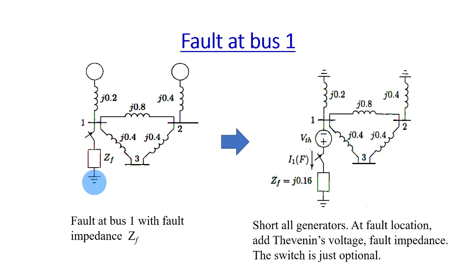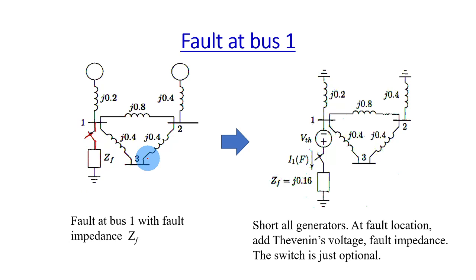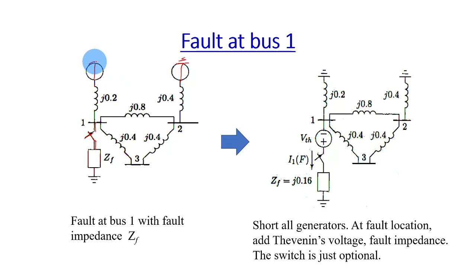You follow the same steps. The first thing you need to do is draw the location of the fault. You can draw it like this as a switch. The fault can be represented as a switch and the fault impedance to the ground. To start with the Thevenin method, we need to short all the voltage sources. There are two voltage sources here, voltage source number 2 and number 1 — we short them to ground.